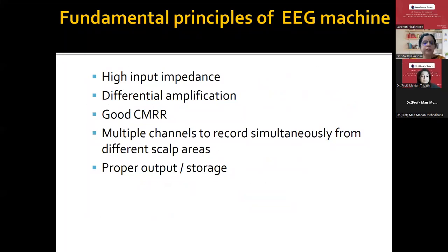The fundamental principles of the EEG machine: it is a high input impedance machine. These are the important qualities. Whenever somebody buys a machine, we should look at these parameters. There should be differential amplification. The machine should have a good CMRR. There are multiple channels to record simultaneously from different scalp areas, and there should be proper storage and output data.